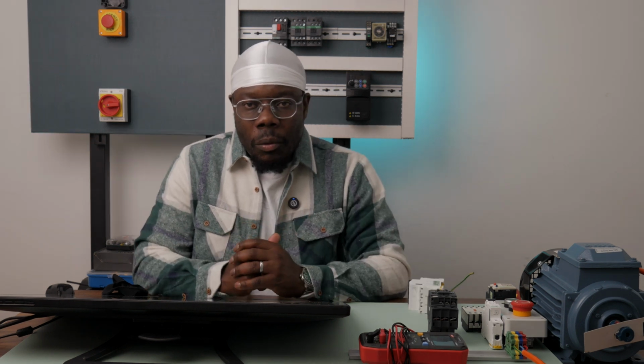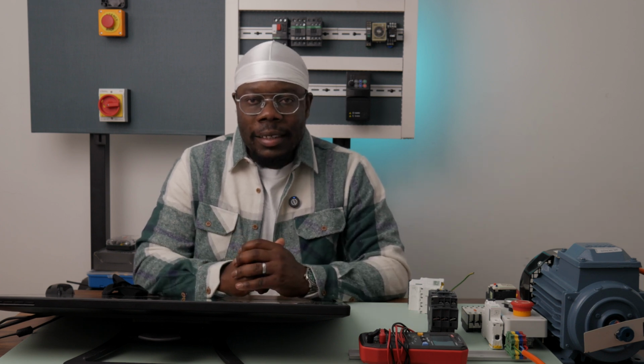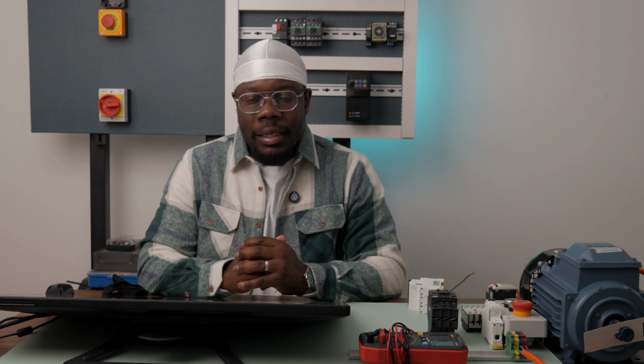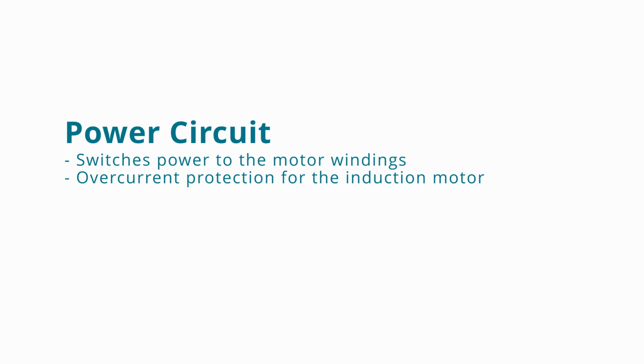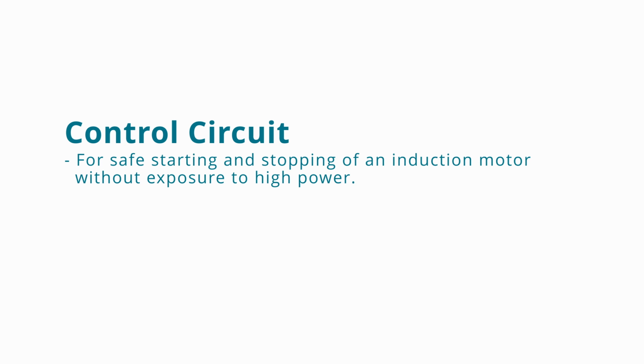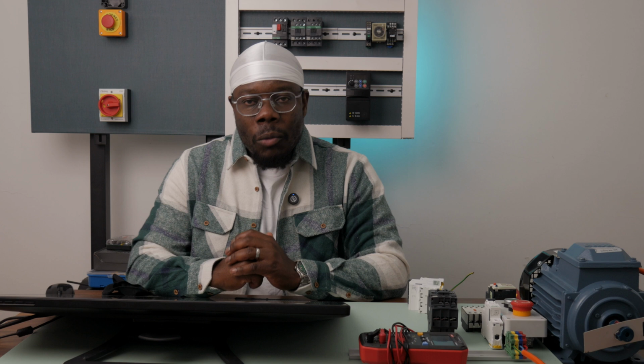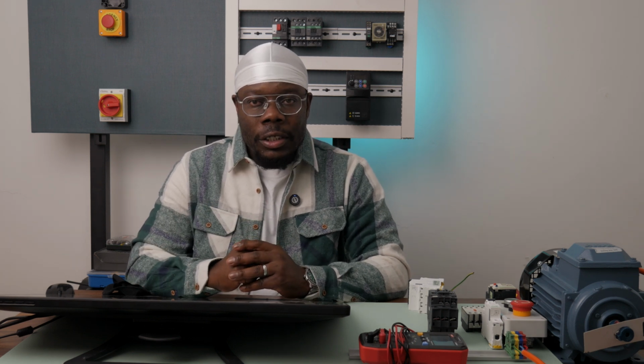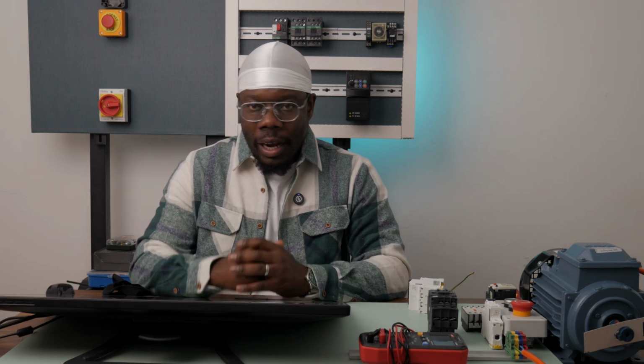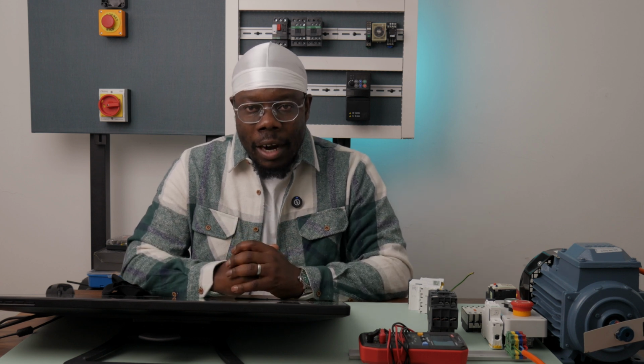Now that we have stated the components that make up both the power circuit and the control circuit of a direct online starter, let's get more in-depth and discuss the purpose of the components in the power circuit. To summarize it all, the power circuit is responsible for switching power to the motor windings and protecting the induction motor against overcurrents. The control circuit allows the safe starting and stopping of an induction motor without exposure to high power. Now, we protect electric motors from two types of overcurrents, which are short circuit currents and overload currents. So let's discuss short circuit currents first.